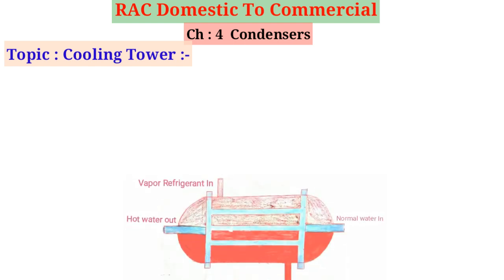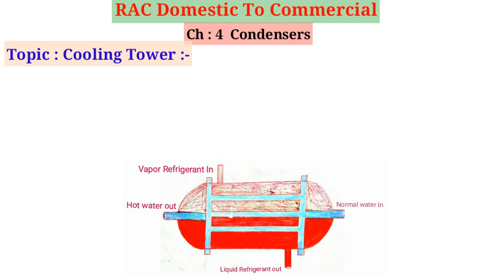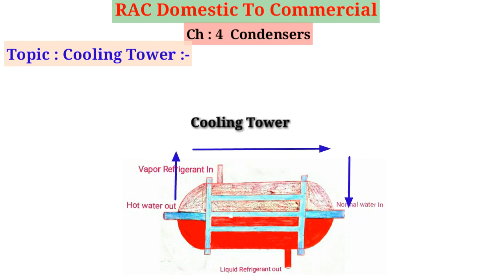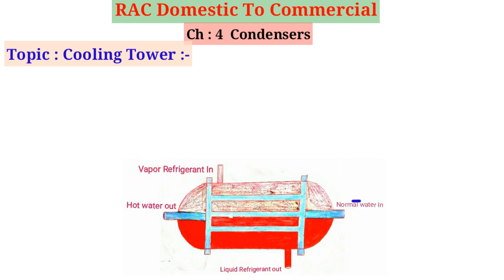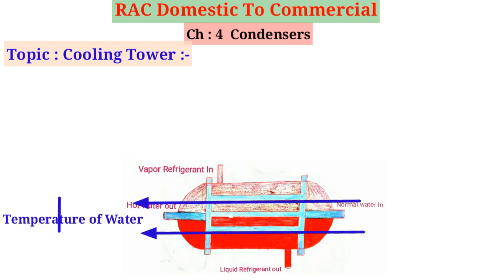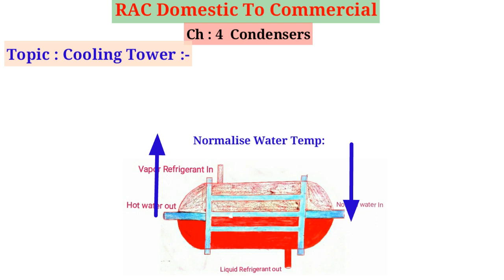When we talk about the water-cooled condenser regarding its use in refrigeration plants, a steady supply of cooling water is most necessary. Natural sources of water are usually limited, and we may not waste such amounts of water circulated in the condenser again and again. Once the water passes through the condenser, it gets sensible heat and the temperature of water rises. So we must arrange to cool the heated water after it passes through the condenser, and then return it to the condenser.